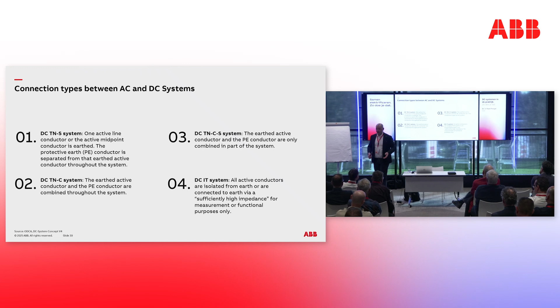One option is combining AC and DC system together in one installation with common grounding as shown here. So this system is grounded on the AC part, and then we have DC. In principle, here you can have a continuation of the AC, so you can have a connection in a house, for example. This would be something also from the connection. You can imagine it's a PV inverter used in a house—they are very often grounded. This can work quite well in small installations.